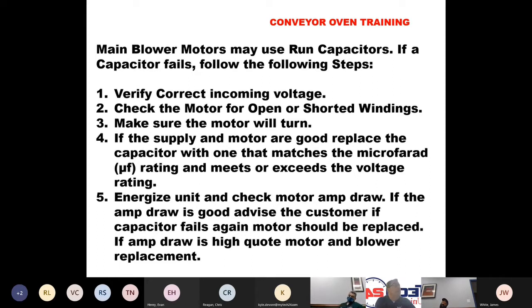Once you have the new capacitor installed, energize the unit and check the motor amp draw. If your amp draw compared to what your data plate says it should be is correct, then let the customer know that if that capacitor fails again, the motor should be replaced. If the amp draw is high compared to the specs on the data plate, go ahead and do a quote for the motor and blower replacement.